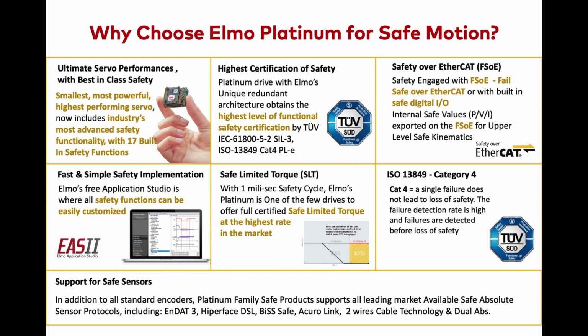They are standard configuration tools for motion, but also for functional safety. The user goes through a guided screen, like a wizard, which guides him on how to configure the system. He selects which safety function he wants to operate, selects whether it's FSOE or the IOs, and makes the parameterization in a safe way. The commissioning of safety on the machine is an important part, no less than the drive itself.